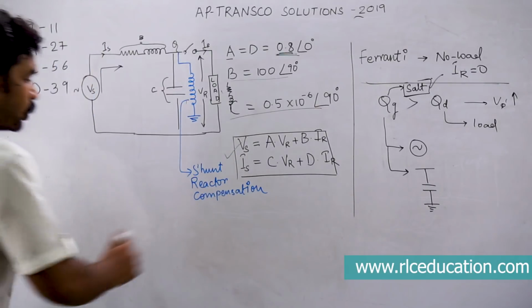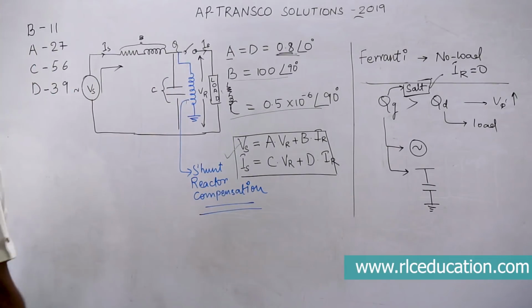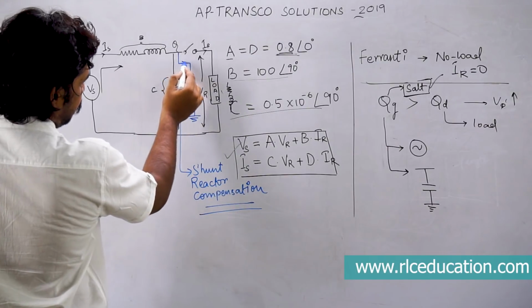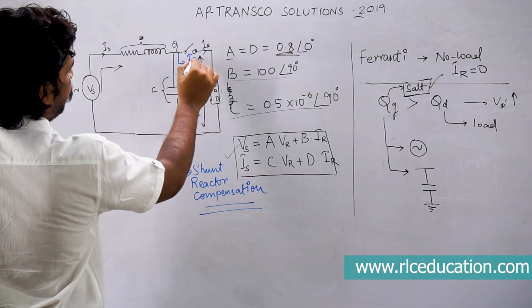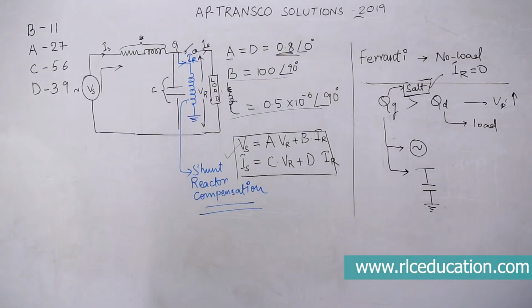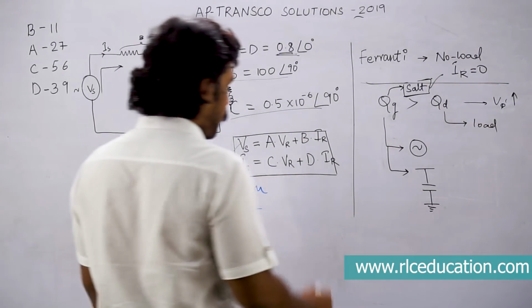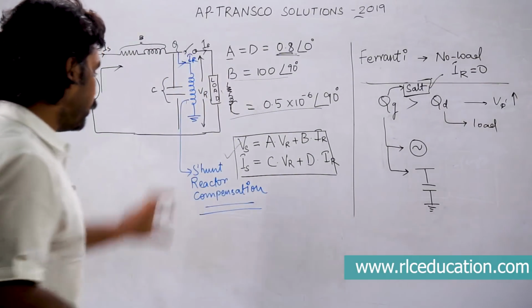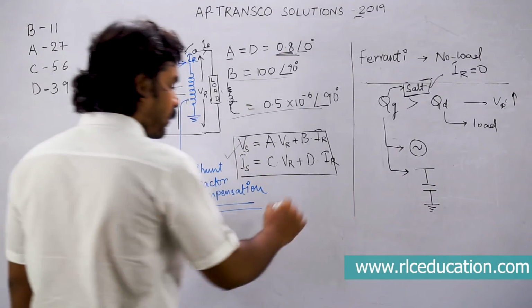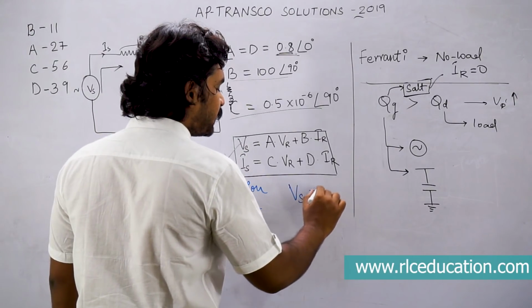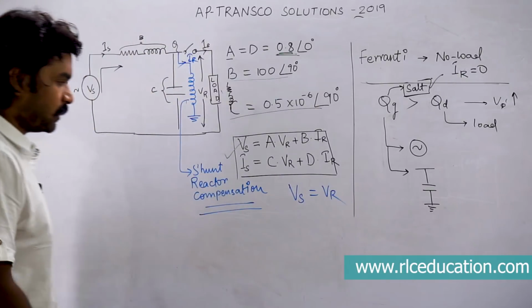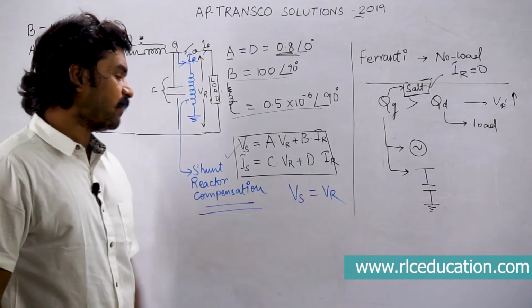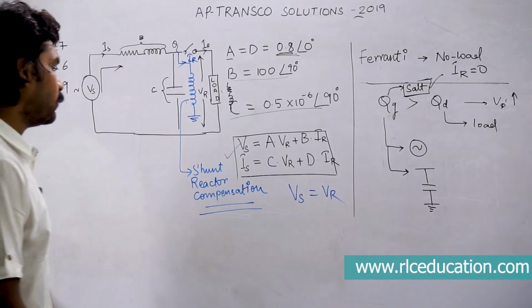So what should be the value of this shunt reactor? If the shunt reactor is connected at the receiving end, the current drawn by the shunt reactor itself will be IR, the receiving end current. The main intention of shunt reactor compensation is to equalize the receiving end voltage and sending end voltage, since the sending end voltage is less, we make VR equal to VS.